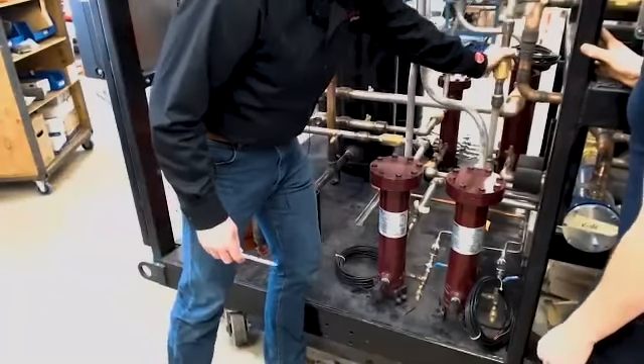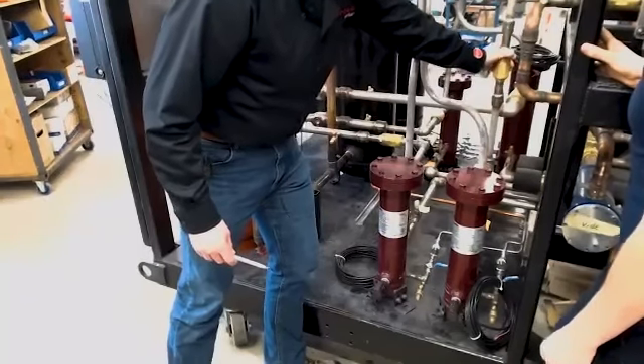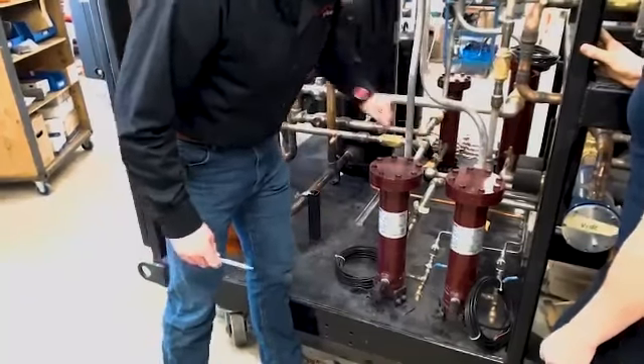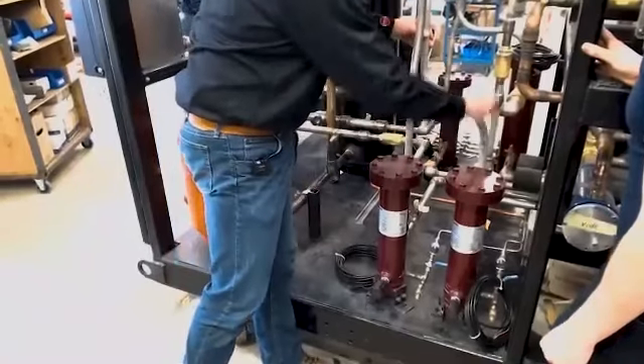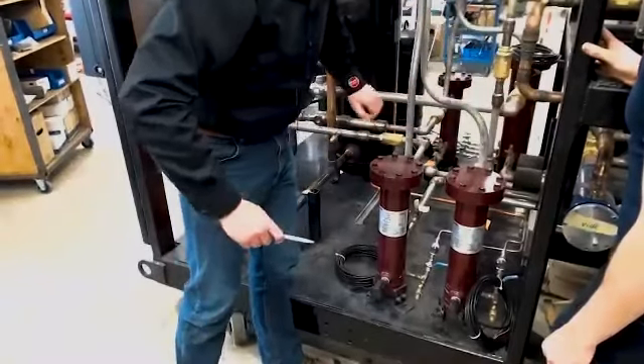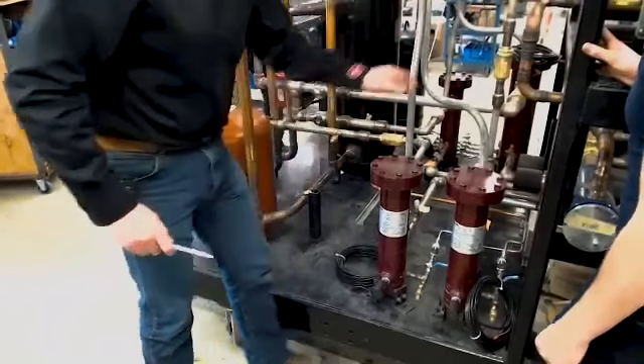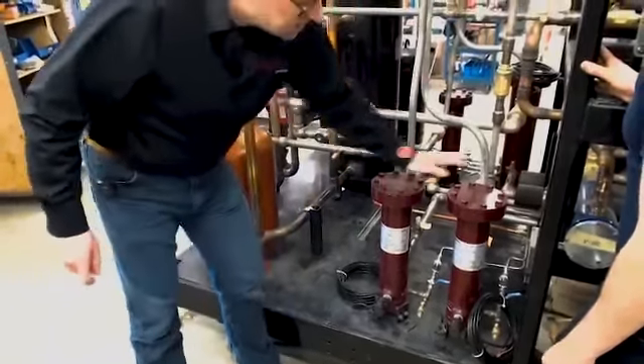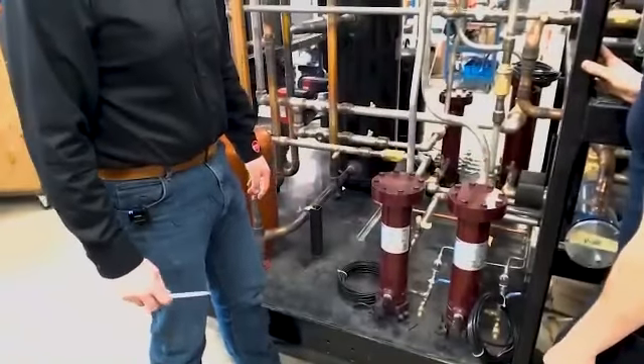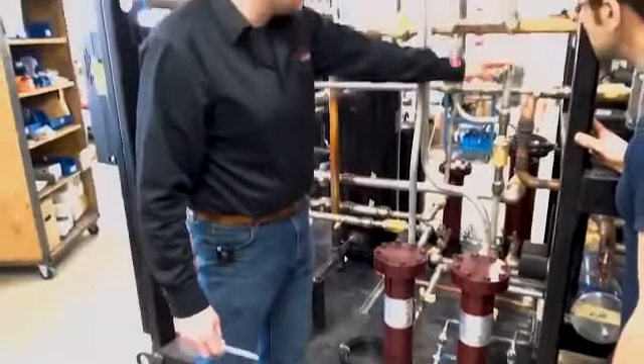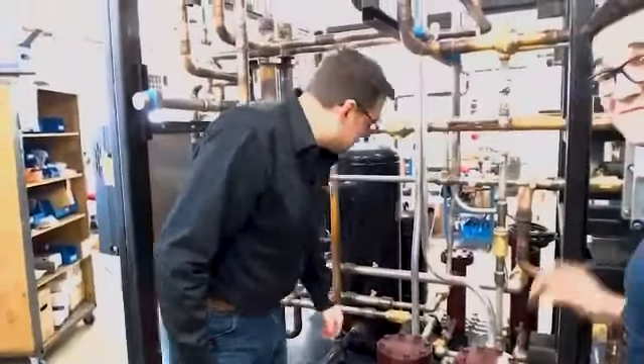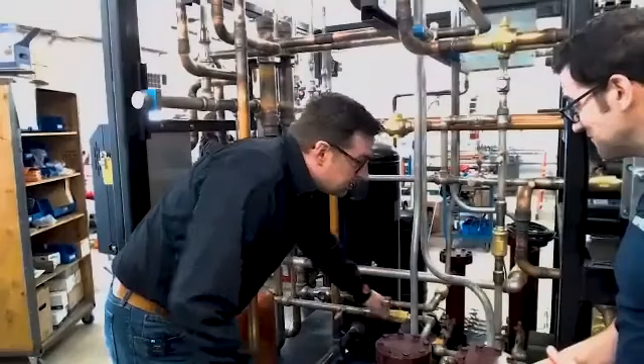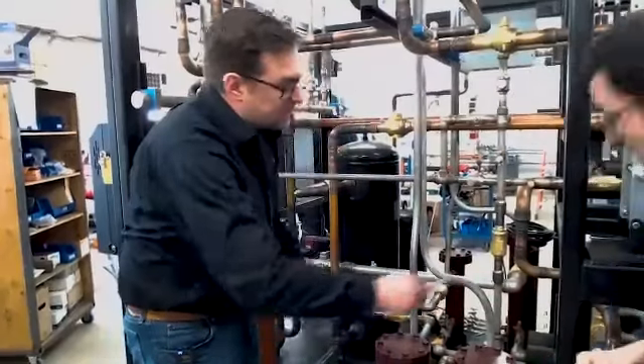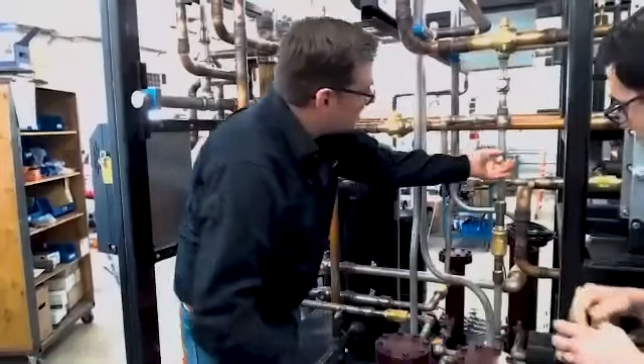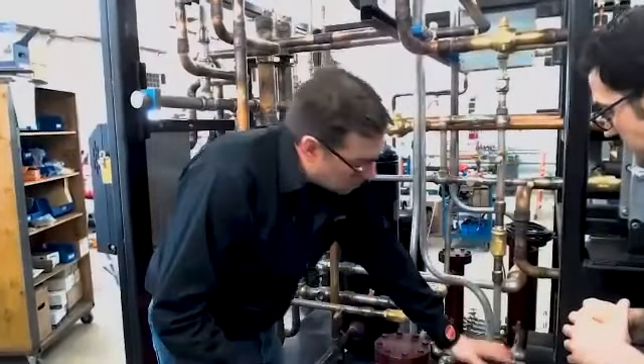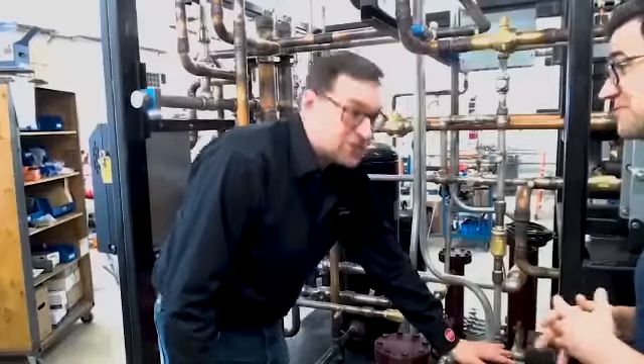It helps prevent that migration. Check valves also create a bit of a back pressure. These are 0.3 bar check valves. Oh, nice. And it helps equalize the various differential pressures in the system. So all our machines that any of you guys will ever work on, you're going to notice that there's check valves on all outlets of the temporary oil separator. Yeah. And in terms of isolation, you're always going to have your purge valves, ball valves down the line. On the manifold line for the compressors, you have a ball valve. So it's as simple as isolating your line, purging it, and then being able to open up your oil separator and changing your filter.